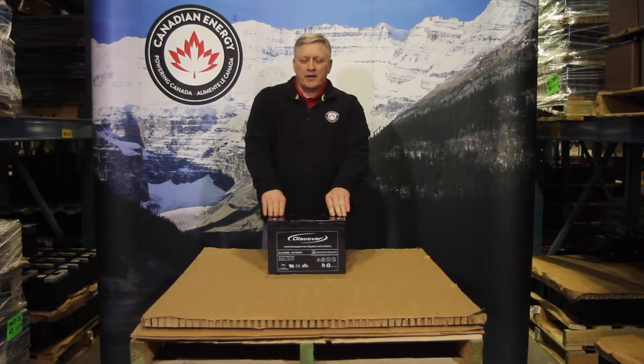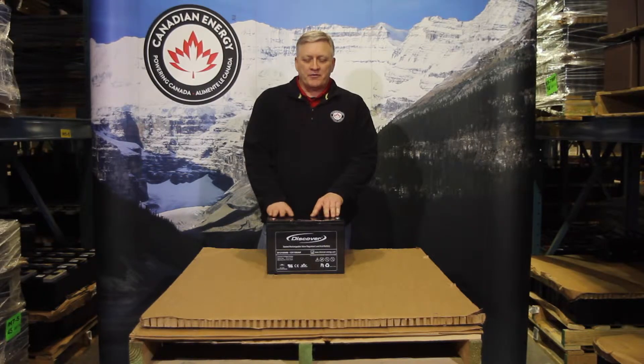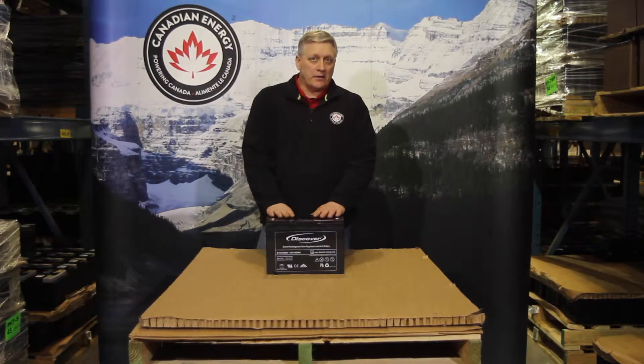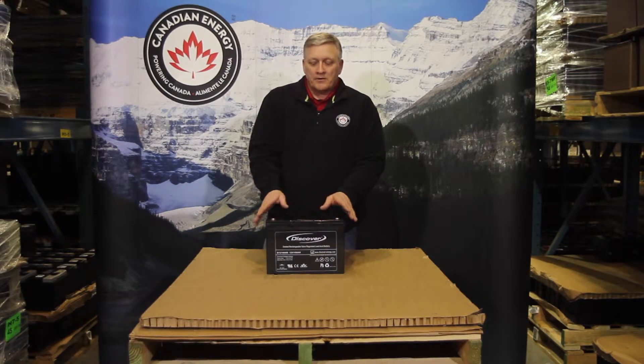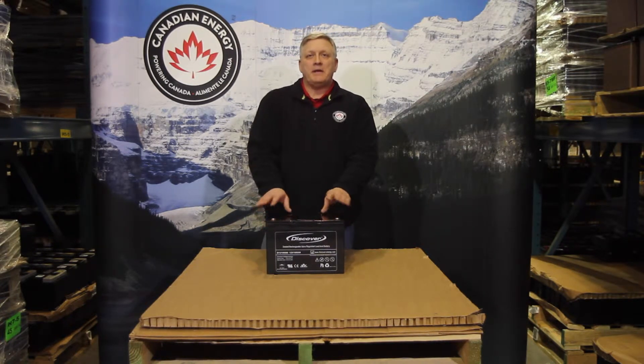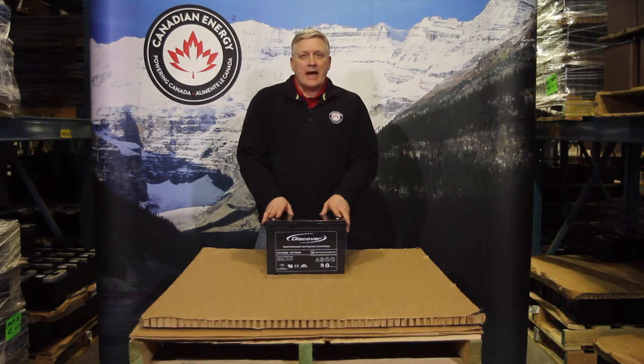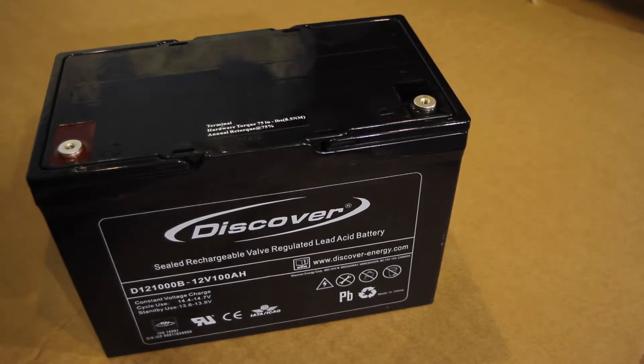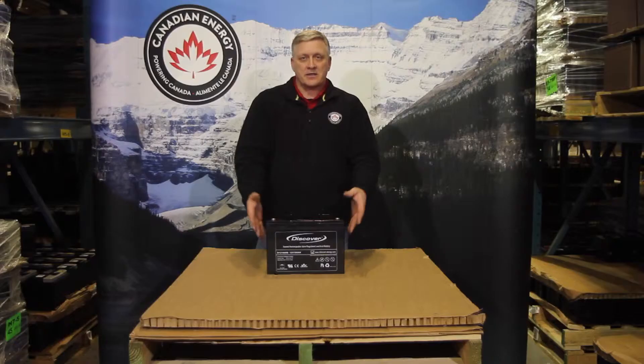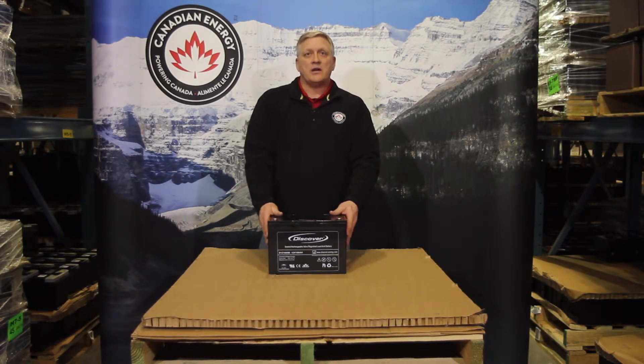What we have here is an example of an AGM deep cycle battery. This product is available through a number of different manufacturers — U.S. Battery, Winfield built by Leoch, Full River — designed for light to medium duty cycling applications where off-gassing is an issue. So if it's going to be in a tight enclosure where hydrogen gas is going to cause corrosion or explosion, you would want to go with an AGM deep cycle battery.